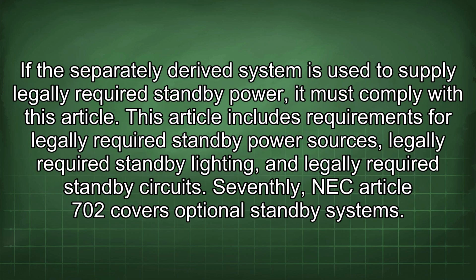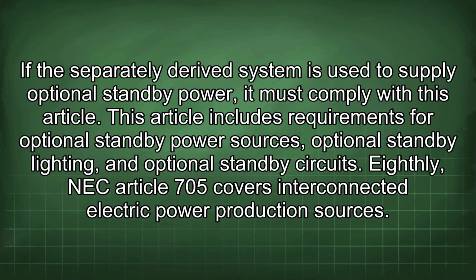Sixthly, NEC Article 701 covers legally required standby systems. If the separately derived system is used to supply legally required standby power, it must comply with this article. This article includes requirements for legally required standby power sources, legally required standby lighting, and legally required standby circuits. Seventhly, NEC Article 702 covers optional standby systems. If the separately derived system is used to supply optional standby power, it must comply with this article. This article includes requirements for optional standby power sources, optional standby lighting, and optional standby circuits.